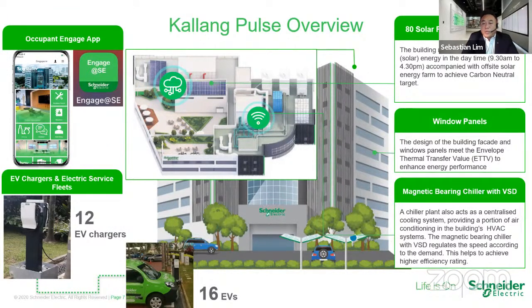With passive energy reduction, the building facade window panels meet the ETTV criteria to reduce the amount of building heat built up during the hot sunny days. Also, with the selection of chiller systems with a higher energy efficiency ratio, such as magnetic bearing chillers, variable speed drive at the water side, and volume control damper at the air side, we enhanced and achieved a higher system performance rating and also optimized the energy profile.